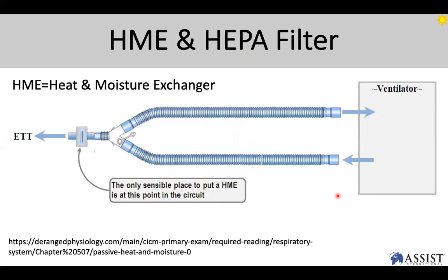So please remember this HME and HEPA filter configuration. HME is basically just the heat and moisture exchange. And then you've got a HEPA filter that filters out particulates from the circuit. This distinction is very important because for the COVID-19 patients that you're treating, we want to use both the HME and the HEPA filter. Otherwise, you will be recirculating the virus through the anesthesia or the ventilator.